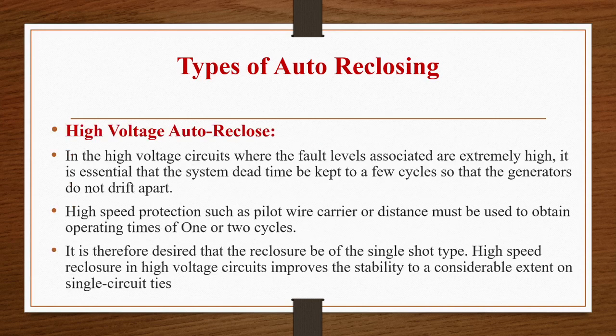Now high voltage auto reclose. In high voltage circuits where the fault levels associated are extremely high, it is essential that the system dead time be kept to a few cycles so that the generators do not drift apart. So high speed protection such as pilot wire carrier or distance must be used to obtain operating times of 1 or 2 cycles. It is therefore desired that the reclosing be of the single shot type.